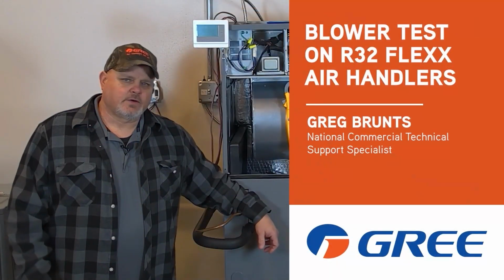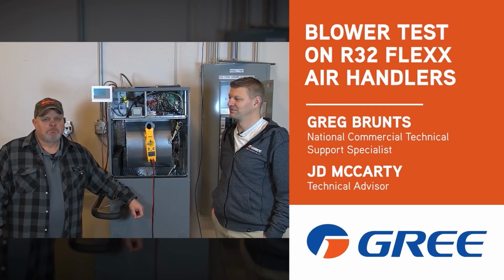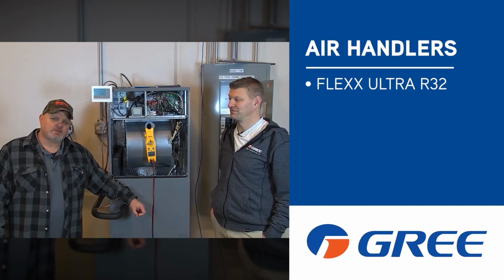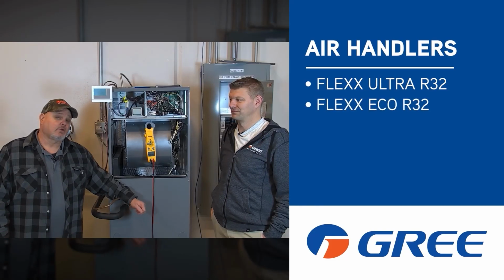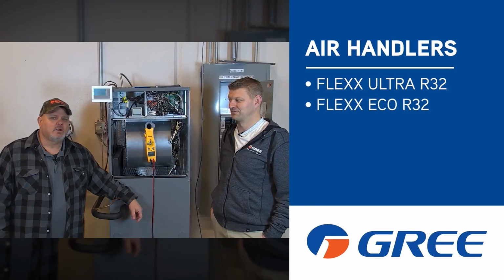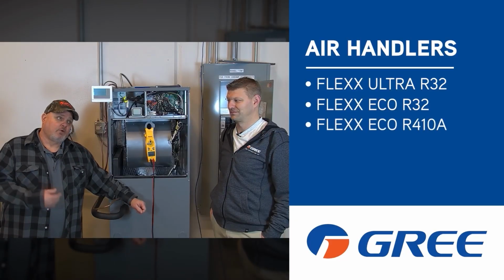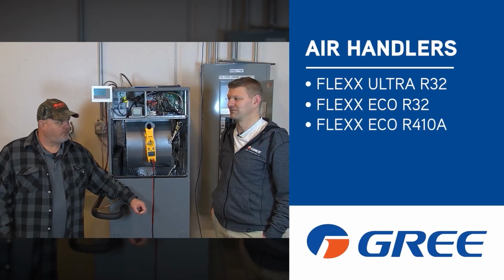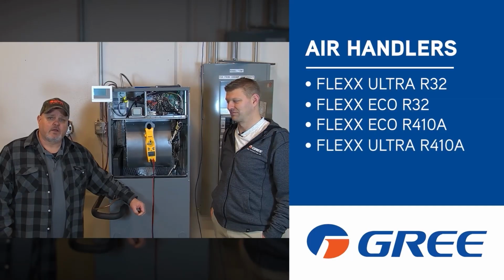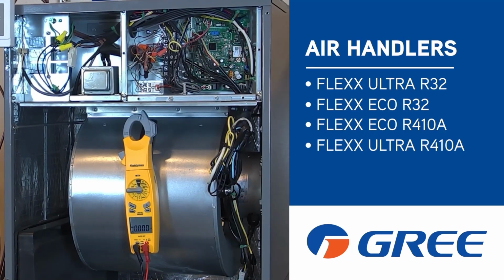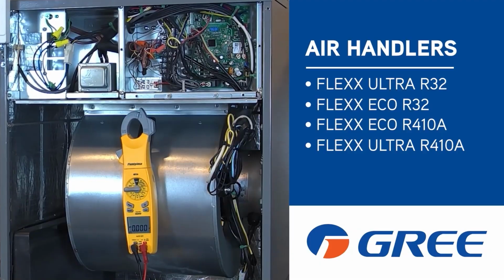Hey everyone, Greg with Gree here with JD. We're going to talk about determining whether you have a motor problem or a board problem with the R32 FLEXX air handler, the R32 FLEXX Eco air handler, or the 410A Eco FLEXX air handler or the 410A Ultra air handler, because the motor used in those is the same in all three.